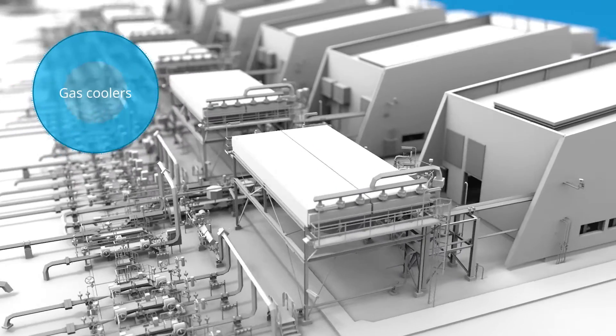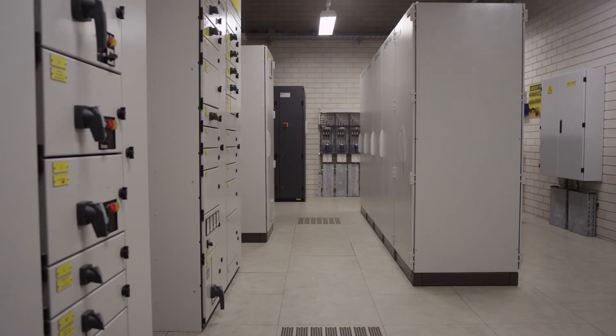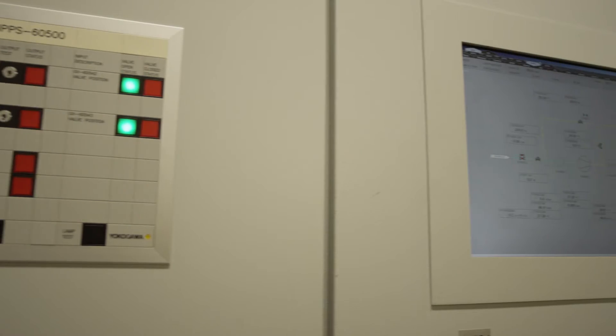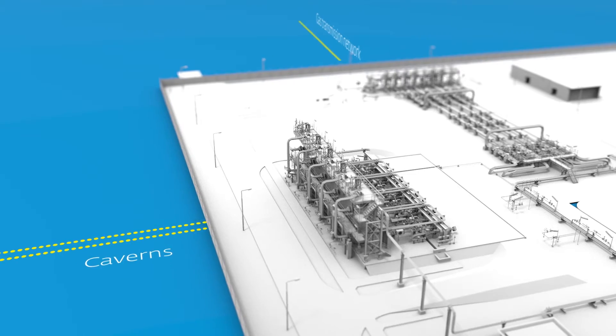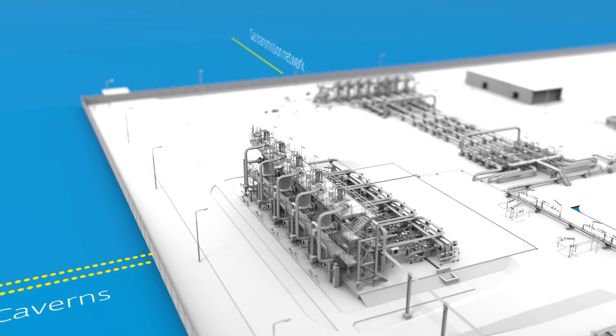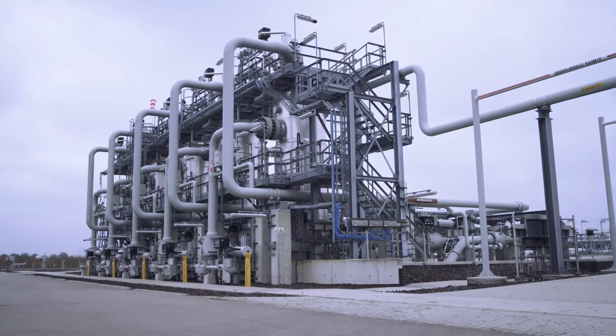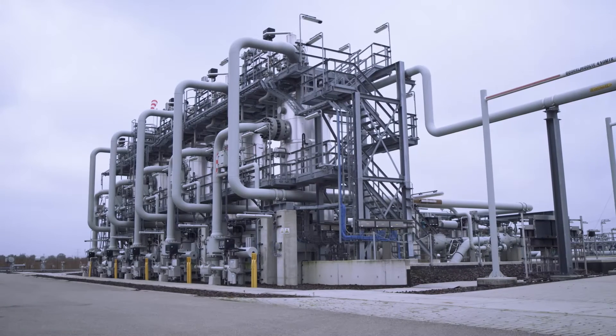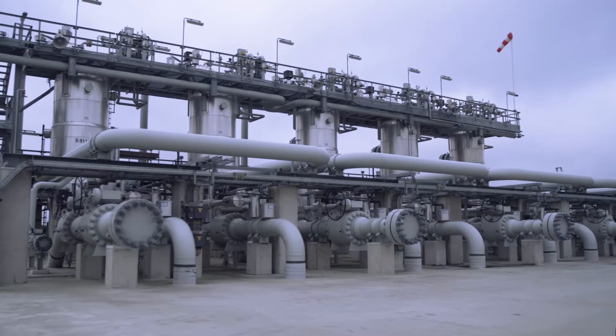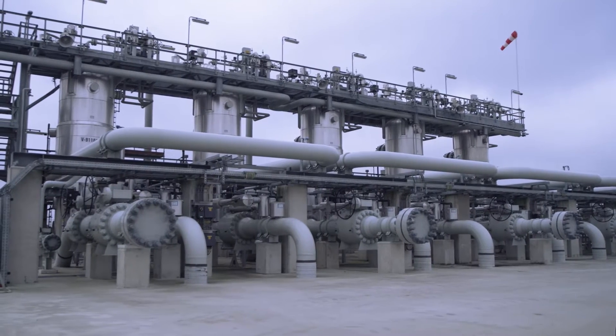The compressors are controlled by pressure regulating stations. Before the gas is supplied to the transmission network, it needs to be treated at the installation. The gas that is extracted from a salt cavern may contain solid particles and liquids. These solid particles are filtered out by sludge catchers.